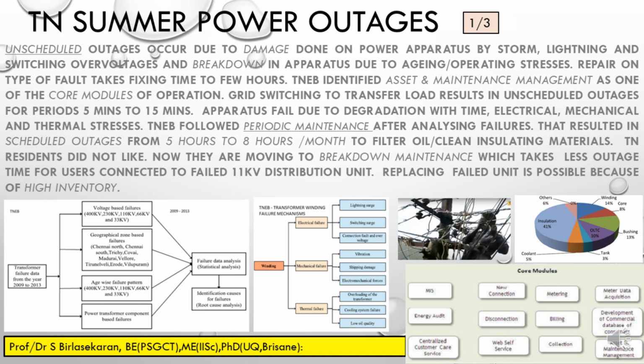TNEB followed periodic maintenance after analyzing the failures, and that resulted in scheduled outages from 5 hours to 8 hours per month to filter transformer oil or cable oil and clean the different insulating materials used in the total system. Tamil Nadu local residents didn't like that, and now they are moving to breakdown maintenance, by which once that 11 kV distribution unit breaks down, they easily replace it. It's possible because of the high inventory available, running to about 3 lakhs in TNEB.